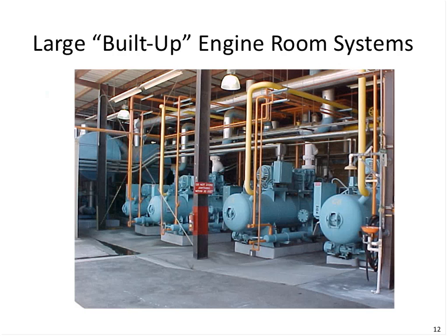If we look at the large built-up systems, and these are usually custom at each site, so here we see compressors as an individual pad-mounted piece of equipment with piping and vessels. These are usually built up at the site. Unlimited tonnage, we can usually add more to these systems relatively easily. We can see a smaller compressor here up to some larger ones, so adding on or staging equipment is usually easily accommodated. We usually get long life here, 20, 30 years, sometimes longer, and also often our highest opportunity for efficiency.